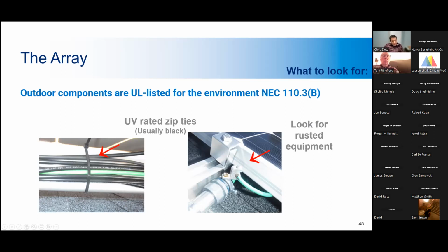All right, this is kind of more on that topic. Like I said, it's critical to use outdoor rated equipment. Most of the equipment for these things is outside, certainly for the array. And the outside environment has harsh elements, which the equipment has to endure 24 hours a day, 7 days a week. Wind, rain, snow, ice, and even the sun itself can degrade equipment very quickly. So, like I said, most of these are warranted for about 25 years. So you need to make sure that all the components that are used in the system have a similar, if not longer, lifespan. And this is coupled with regularly scheduled inspection and maintenance to ensure that potential problems are detected before they cause serious issues. So on the left here, you can see that the wires are fixed in place with a black zip tie.